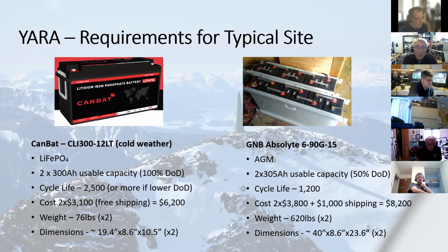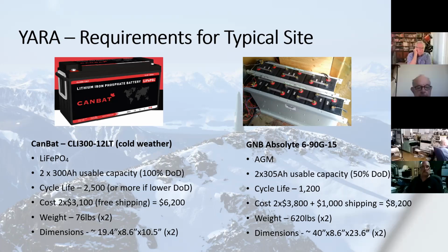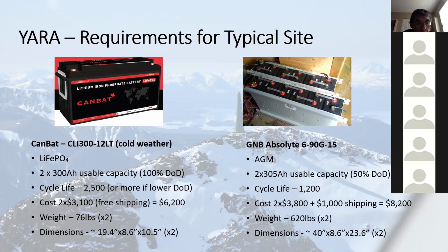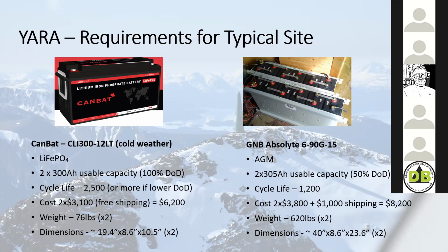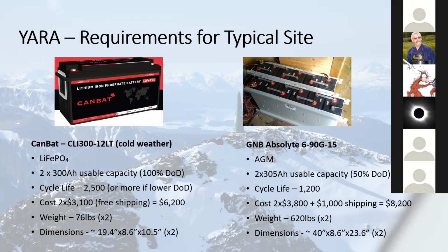They make a 300 amp hour 12 volt cell, so 2 of those, and you can obviously use 100% of their capacity. They have a cycle life of 2,500, which is the manufacturer's prediction at 100% depth of discharge. If you cycle them less than that, the number of cycles increases. Right now they cost about $3,100 each, and they don't charge shipping anywhere in Canada, so a total cost of $6,200. Each cell weighs 76 pounds and is about 20 inches by 8.5 by 10.5.